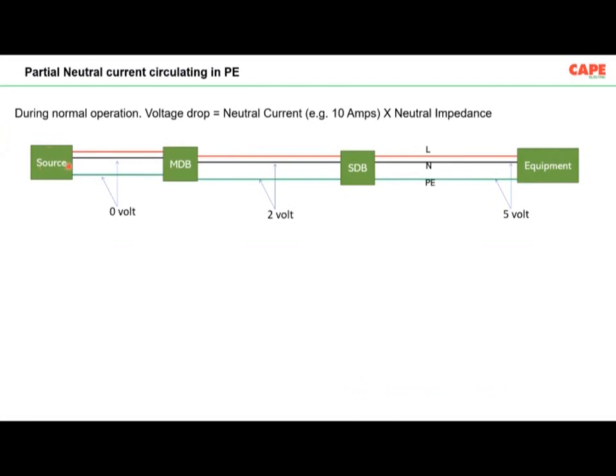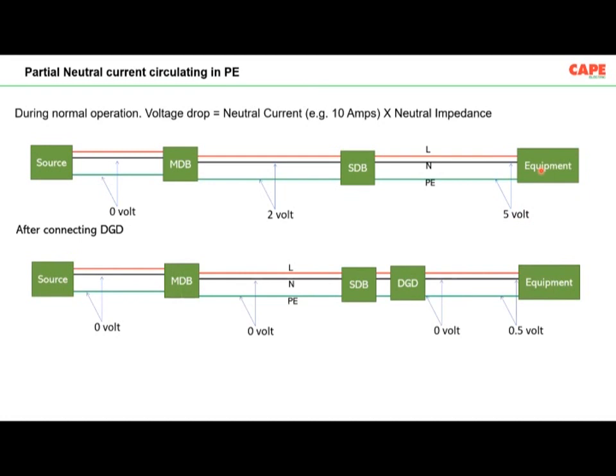There is a source, let us say in an IT building, and the neutral is earthed. The potential between neutral and earth closer to the source is near 0 volt. After the MDB, probably the neutral and earth voltage is 2 volt. Near the equipment, the voltage between neutral and earth is sometimes 5 volt. The equipment vendor, if it is a sensitive equipment, always says that my equipment will fail if the voltage is 5 volt. So they always demand a voltage of less than, say, for example, 1 volt for your equipment. Otherwise, your equipment will fail.